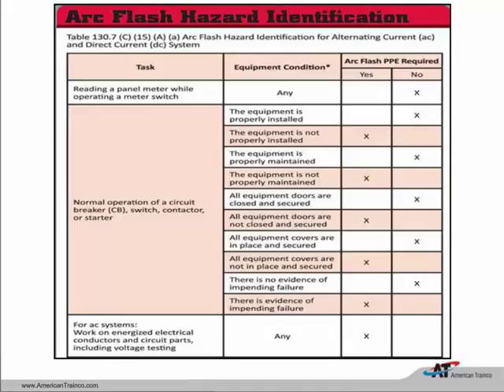To go on to that, let's come down to where it says for AC systems, work on energized conductors and circuit parts, including voltage testing. So they don't care about the equipment condition here. If you have exposed energized conductors or parts and you are troubleshooting, the X will always be under the yes column. You will be wearing arc flash PPE under that scenario.